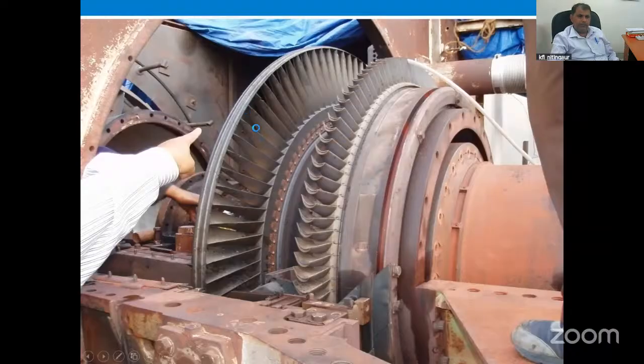Here you can see that this is the turbine, a two-stage gas turbine. First one stage is this, second one is this. If you see that there is a dent in the buckets of the turbine, it means these buckets have completed their service life and need to be replaced with new ones. Also, we check the clearances between these buckets and what are called the shrouds. So care should be taken during the maintenance of the gas turbine.